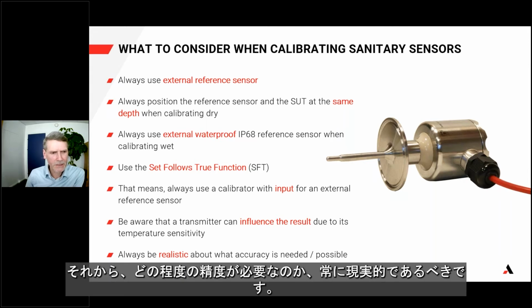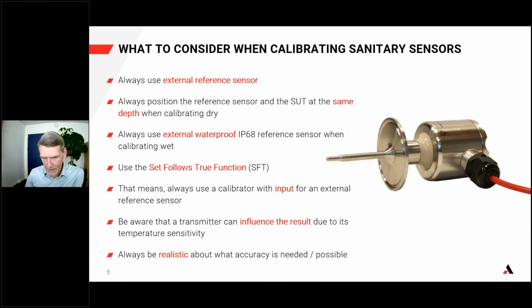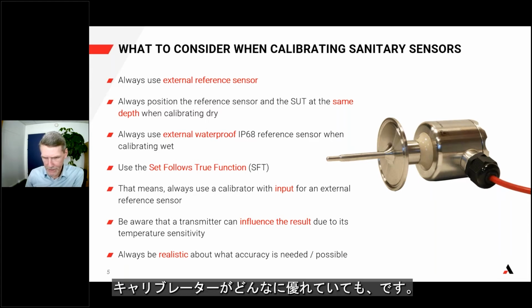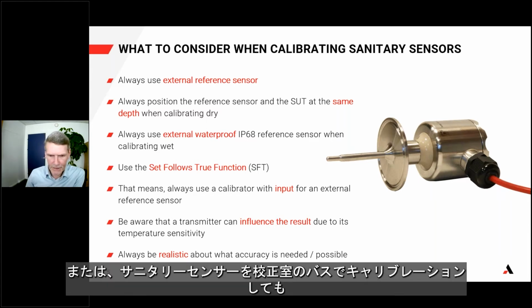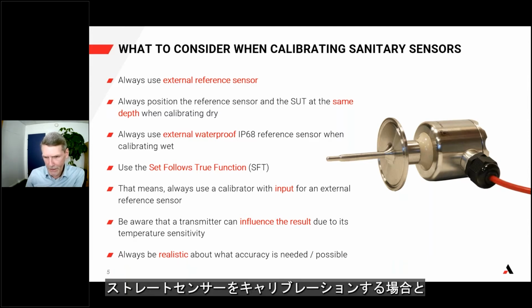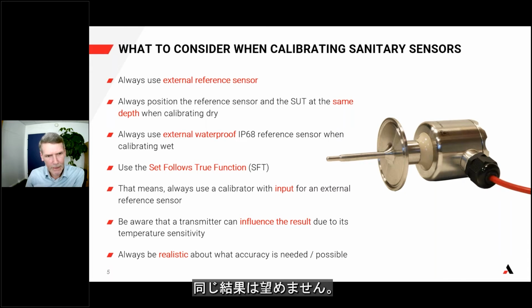Then you should always be realistic about what accuracy is needed. No matter how good your calibrator is, or even if you calibrate the sanitary sensor in a laboratory bath, you cannot expect the same results as you can when calibrating straight sensors.